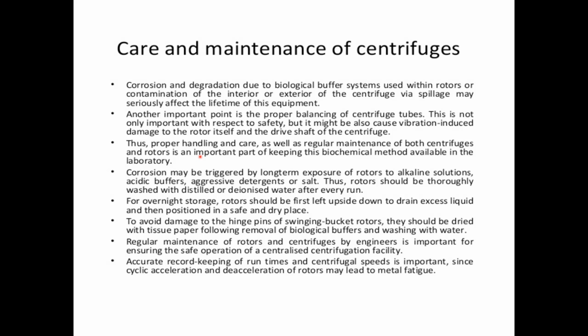Learn how to use these machines. So when you come to a lab and you do your first centrifugation round, ask an experienced researcher in the lab, a postdoc or PhD student, or the technician in the lab to show you how to deal with the instrument. How long does it take until the vacuum is built up, and why you should keep the rotors cool at 4 degrees in the cold room, what measures you should take to clean the rotors afterwards, which liquids you are allowed to use for cleaning the rotors, which are not too aggressive and cause corrosion or degradation of the material, and many other things that you should take into consideration.